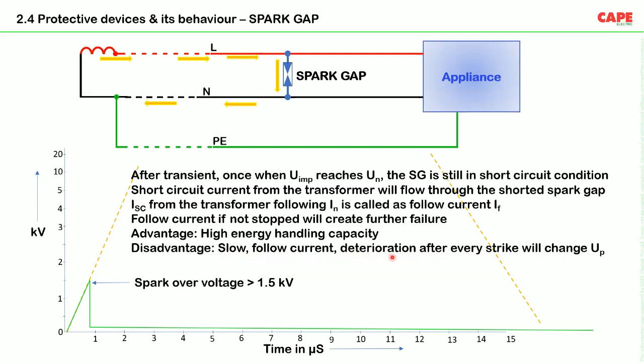This is also written in the standard for spark gaps. After every sparkover, some portion of the metallic electrode melts and it changes the characteristics. These are documented in this standard. So each of these components has its own advantage and disadvantage. For example, an MOV's advantage is that it is faster. The disadvantage is it will die on its own whenever there is a temporary overvoltage. The advantage of a spark gap is its high energy handling capacity. It can handle large current, but it is slow. It has follow current and it deteriorates after each and every surge current.